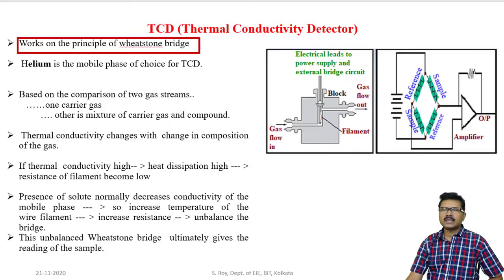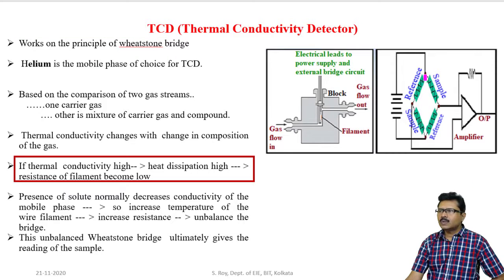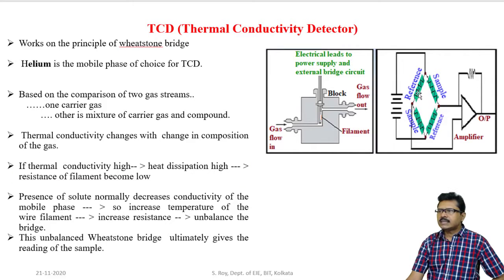This detector is based on comparison of two gases — one is carrier gas and the other is a mixture of carrier gas and compound. Thermal conductivity of different gases are different, so a change in composition of gas causes a change in thermal conductivity. For a resistive element, when current passes through a resistance, the temperature increases and it produces heat. If the conductivity of the surrounding atmosphere is higher, heat dissipation will be higher; if lower, heat dissipation will be lower. Using this property, the thermal conductivity detector produces output.